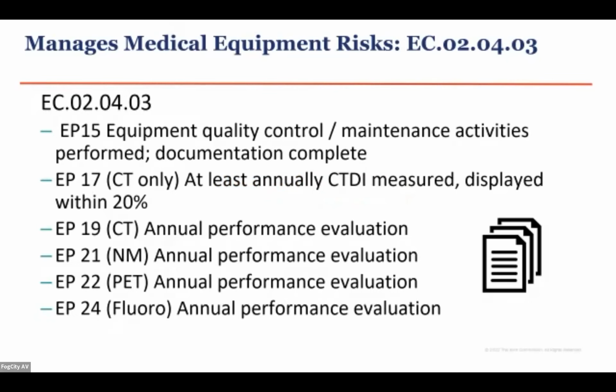Those are tests that a qualified medical physicist or nuclear medicine scientist or MRI scientist can do to look at how well your equipment is performing in those imaging modalities. Now, there's a difference, although if you go through the manual and look at exactly what's being measured, you'll say, gee, this is an awful lot like what ACR accreditation looks at. Yes, they're pretty much the same parameters.